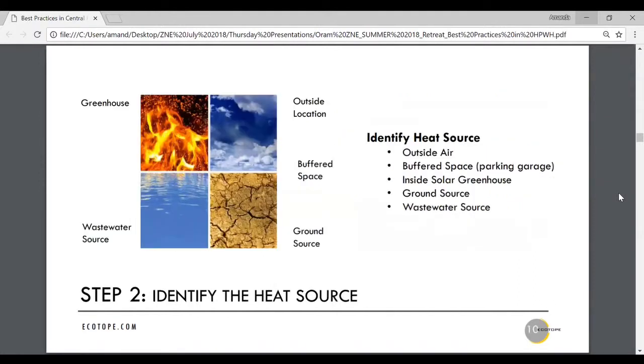The next piece would be to identify the heat source. There are several options, but outside air is kind of the easiest. A buffered space, like a below-grade parking garage, is where we've had the most success. So on big 5-over-1, 5-over-2 apartments, we put the heat pumps in the garage. We never see lower than 50 degrees in a garage. Keep in mind in Seattle, design temp is 23.